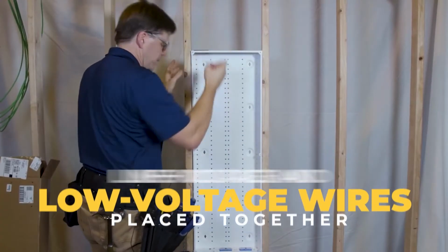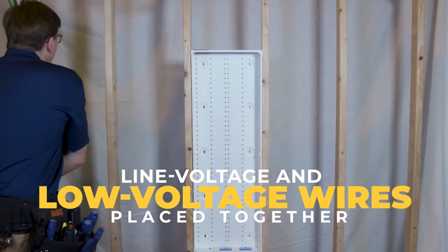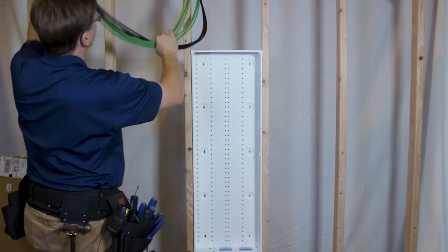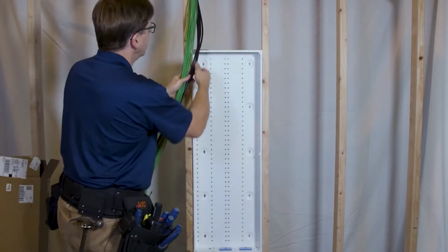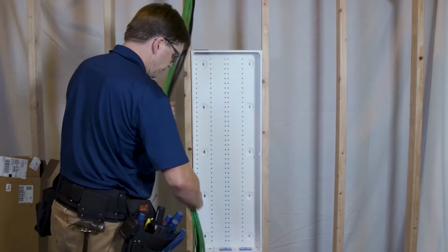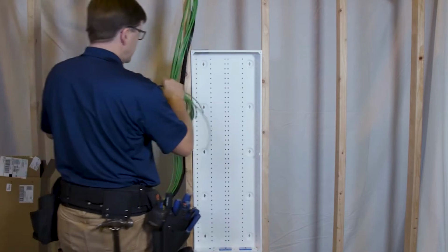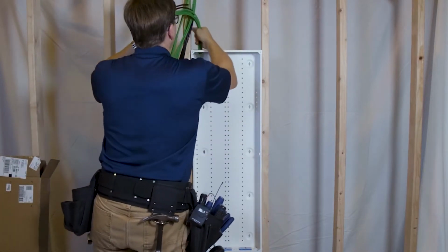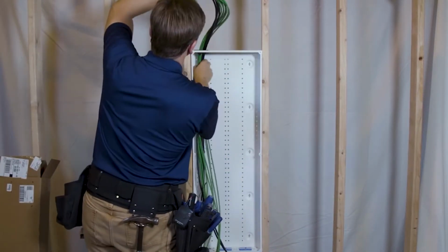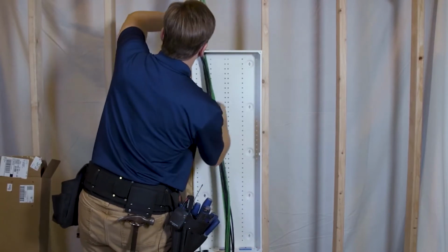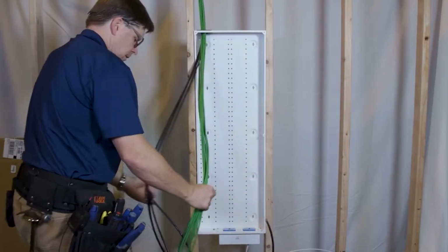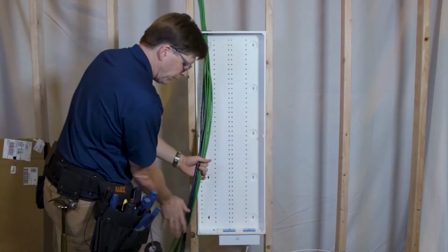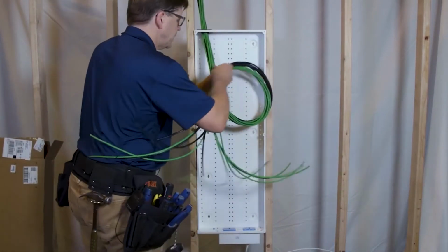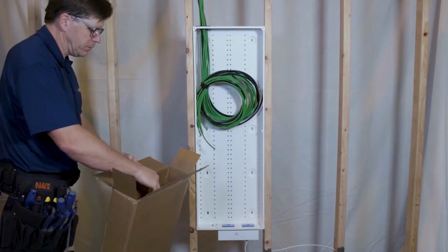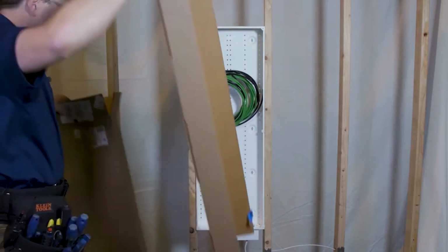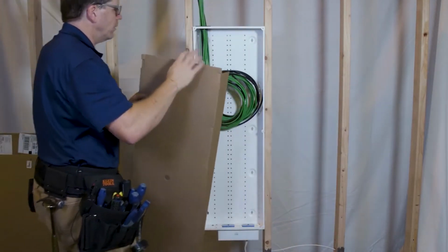Line voltage and low voltage wires placed together. Placing line voltage and low voltage cables together is one of the most typical wiring blunders committed by people installing electricity in new building structures. Not only will this cause electrical interference with numerous devices, but if the cables come into touch, the structure's equipment may be harmed. Furthermore, a fire could start. The parallel runs need to be at least 6 inches apart to avoid this wiring blunder. Furthermore, unless the box has a defined divider for the multiple voltage levels, the various voltages should not be contained within the same box.